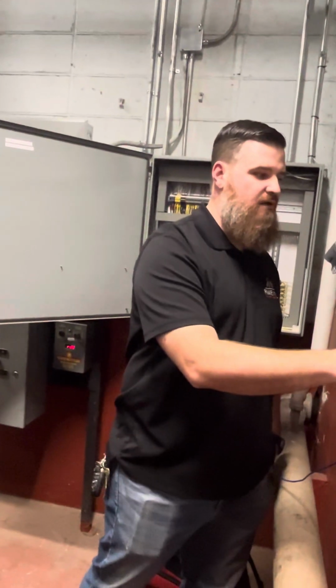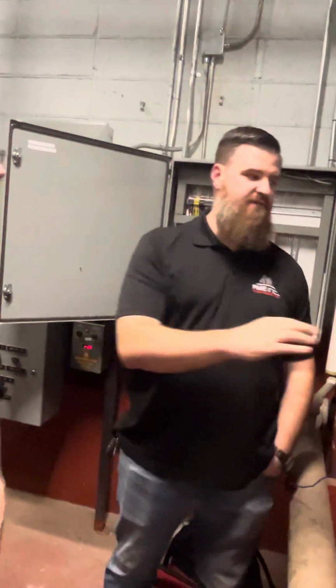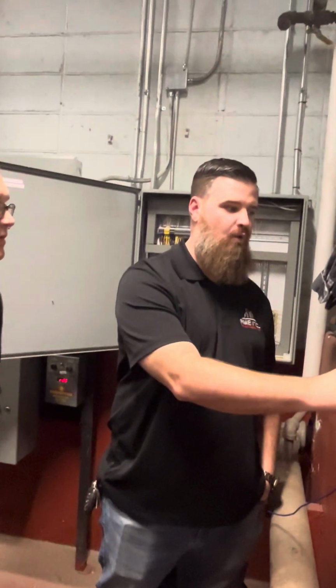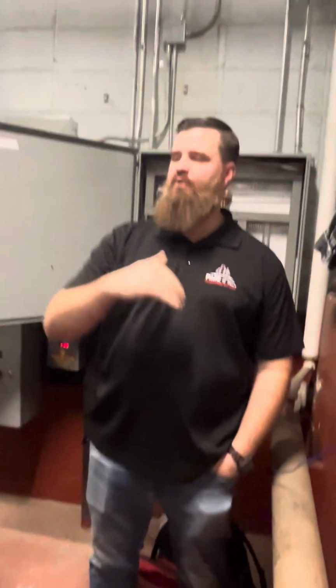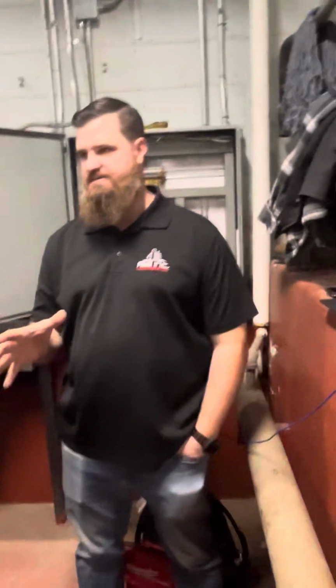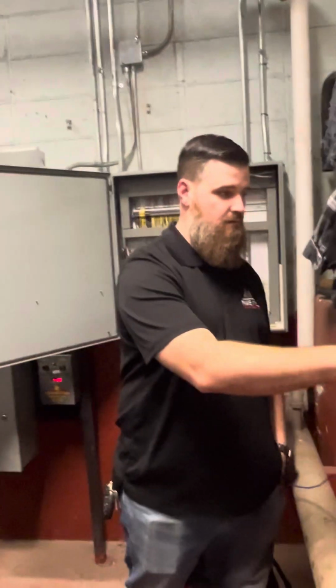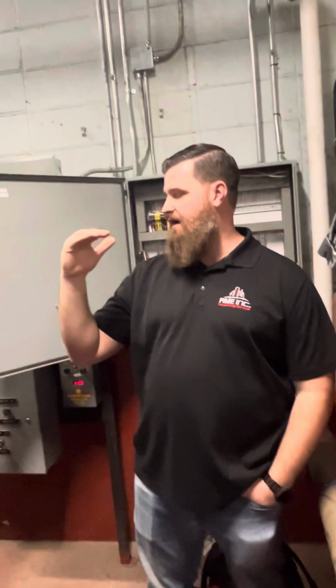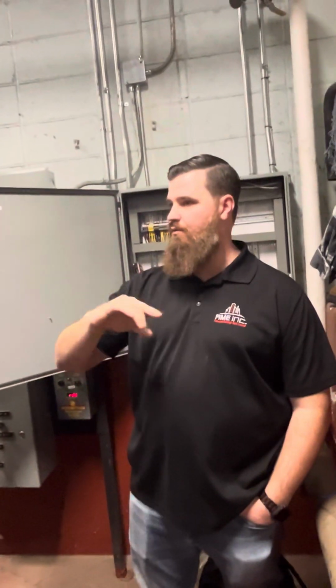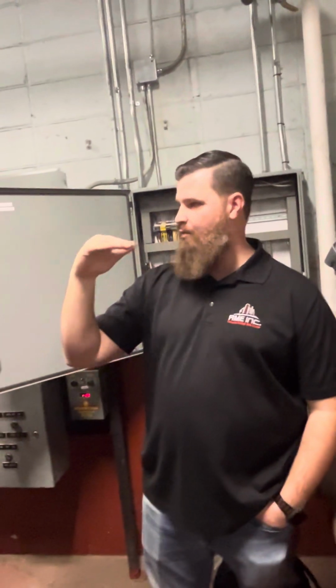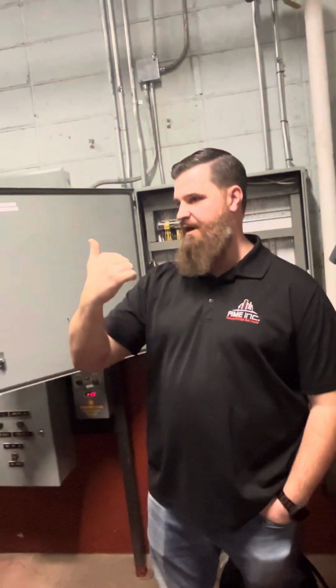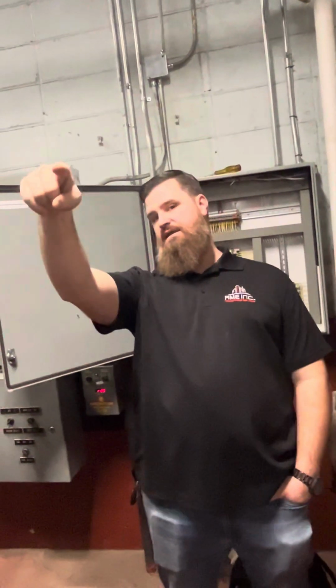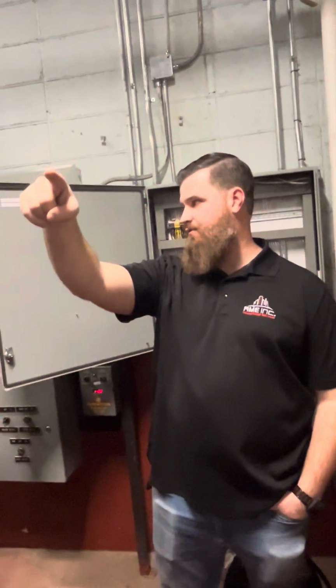All right. Now, lead boiler set point dead band. Okay, 1 pound. You have the ability to adjust this right here if you want, but it's a 1 pound differential. So lead boiler is going to kick on when we hit 2 pounds. It's going to kick off when we hit 4 pounds. That makes sense. Could you say it again? Lead boiler is going to kick off. It's a 1 pound differential, so plus or minus 1. So we hit 2 pounds, lead boiler comes on. We hit 4 pounds, lead boiler goes off. That's why I need the pressure to be allowed to go higher than 3 pounds.